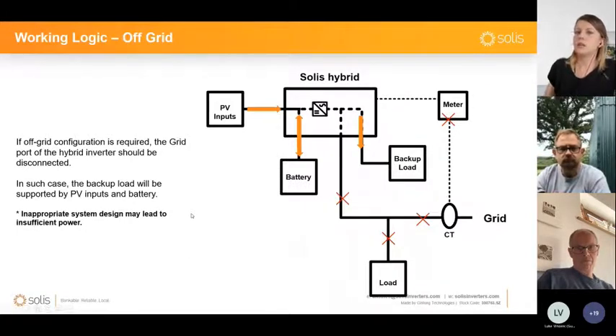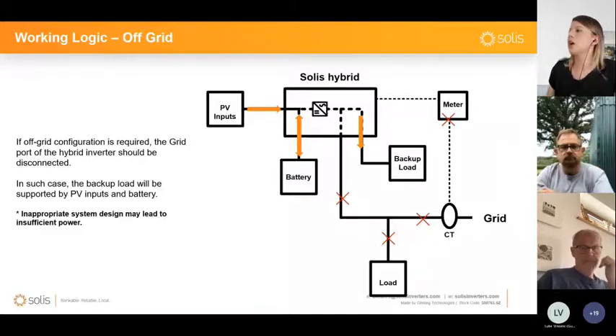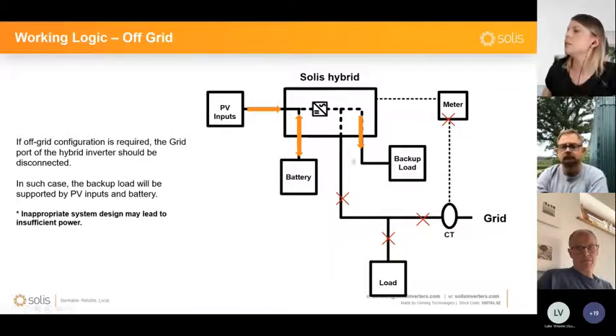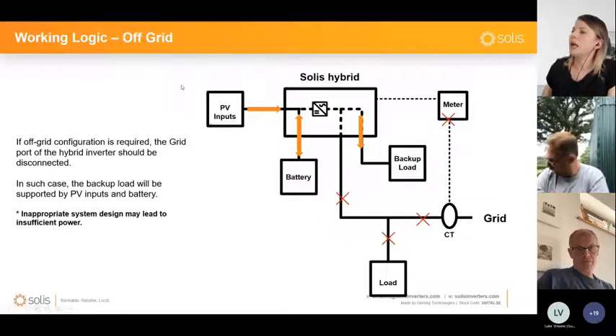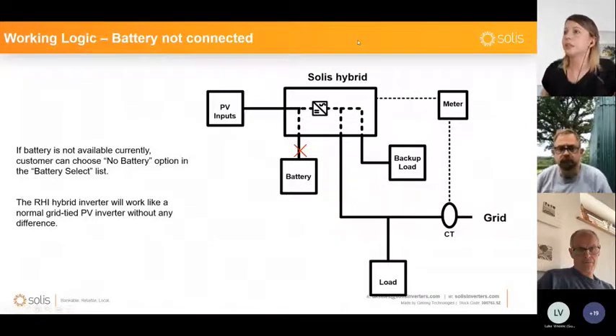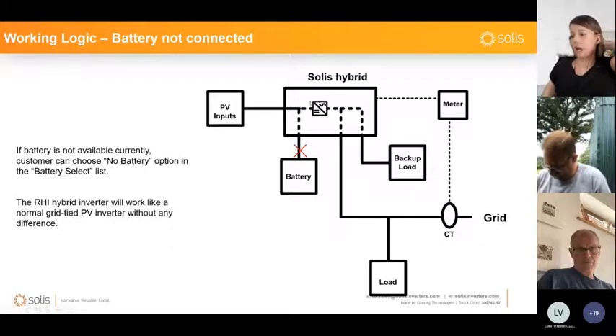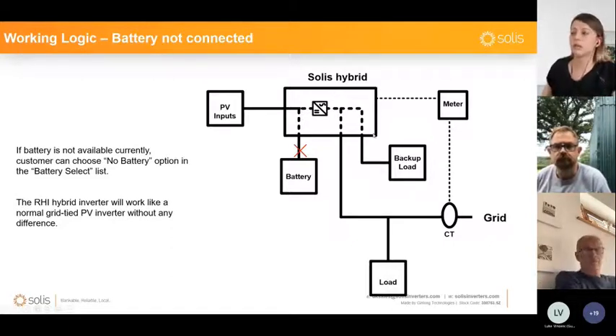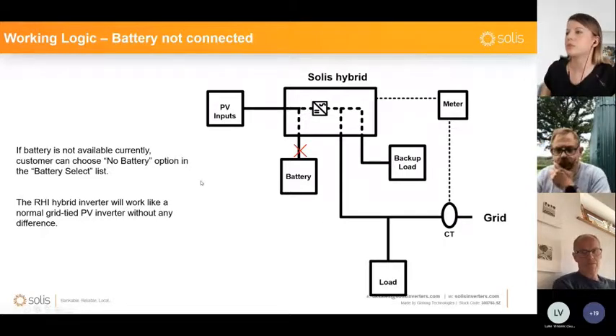So the working mode for the off-grid. Here you don't even need a meter to be installed with the Solis hybrid. The connection will only be on the backup load, with the loads that are connected as critical load. The hybrid is the one that is actually creating the grid. And you're going to have the PV inputs and the batteries, and all this doesn't even have to exist. But of course, for these types of systems, you have to be careful how you design the capacity of the battery in order to be able to supply those critical loads throughout all periods.